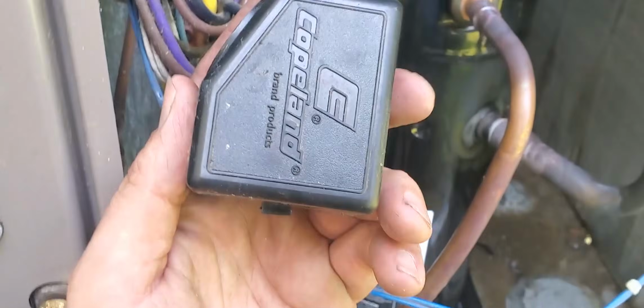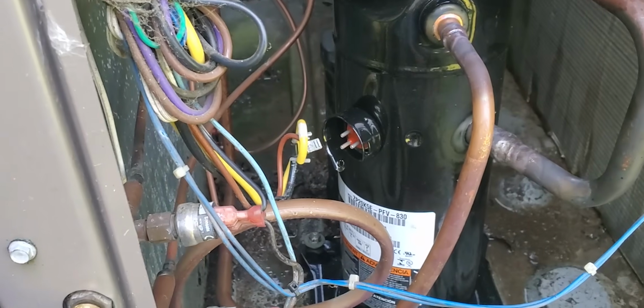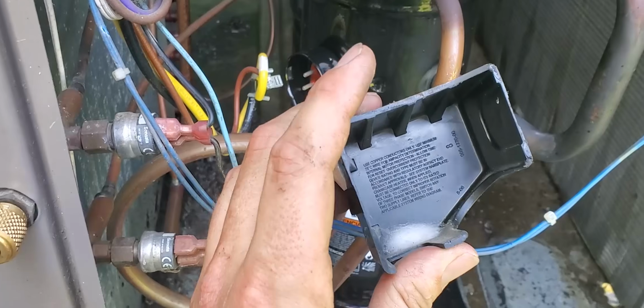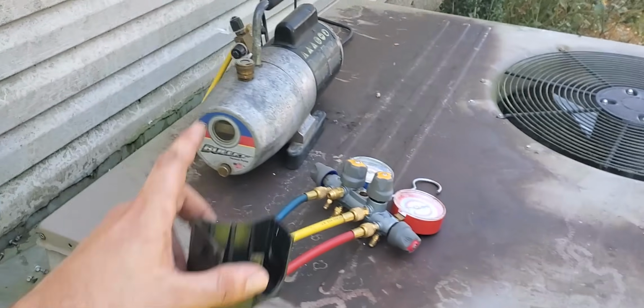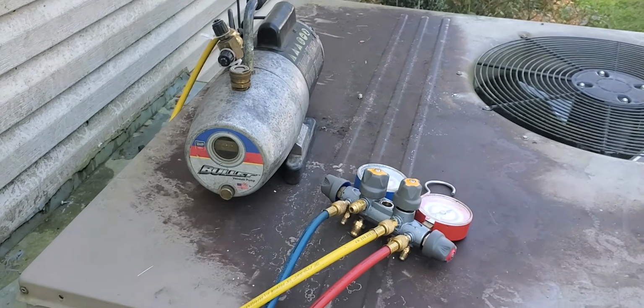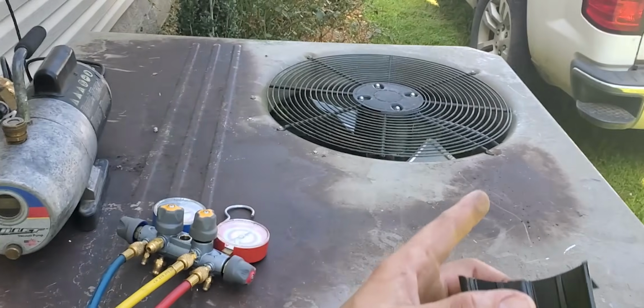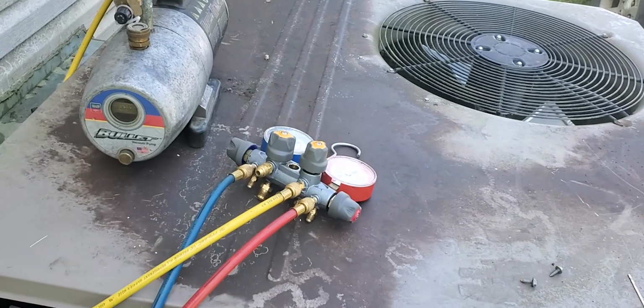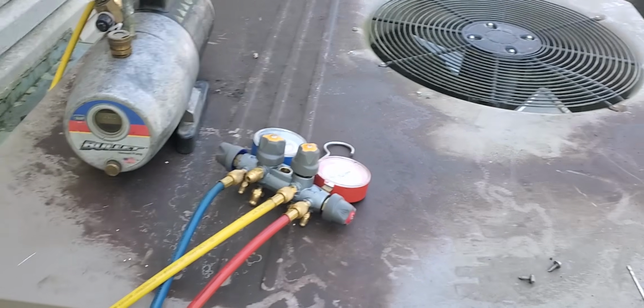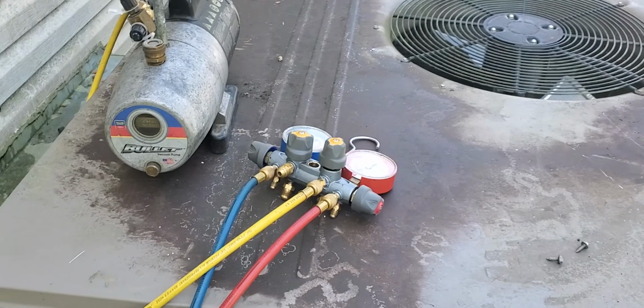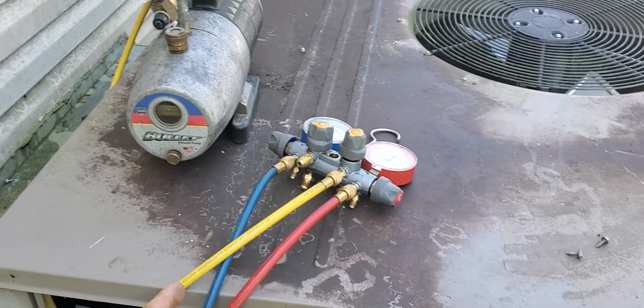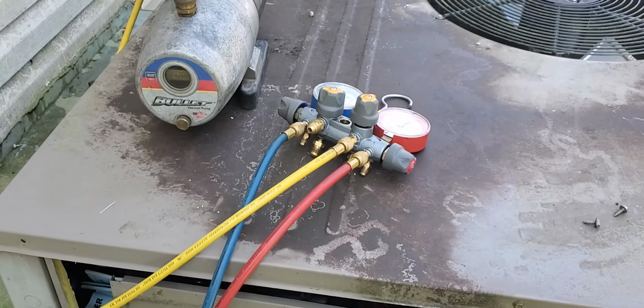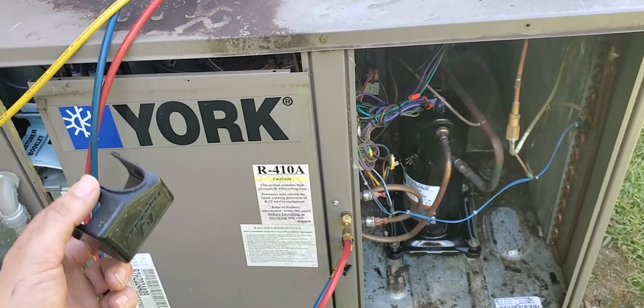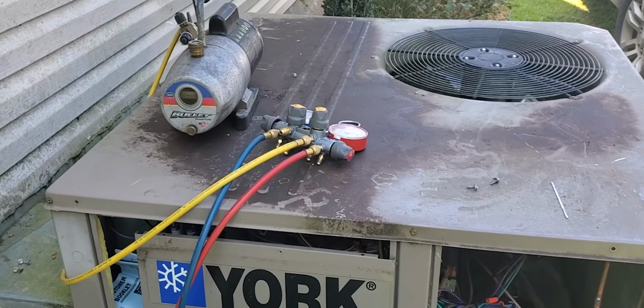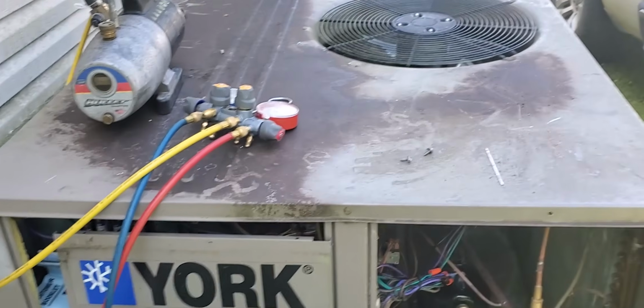pumped down. Make sure that you do a triple evac. If you don't know what that is, it is where you pump the unit down for 15-20 minutes. You put nitrogen back on at a low setting, 15 pounds, just to break the vacuum, and then you do that again. And that helps to pull down to the microns that you need, which is usually around 500 microns. If you don't have a micron gauge, get a micron gauge.